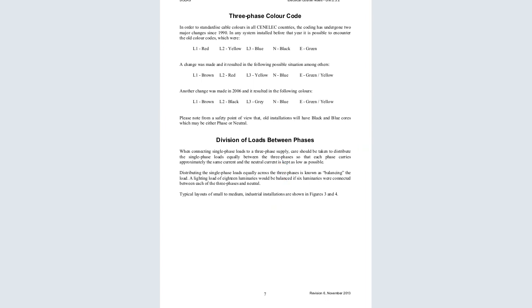Now, the division of loads between phases. When connecting single-phase loads on the three-phase supply, care should be taken to distribute the single-phase loads equally between the three phases so that each phase carries approximately the same current and the neutral current is kept as low as possible. Distributing the loads equally across the three phases is known as balancing. So we have something called load balancing.